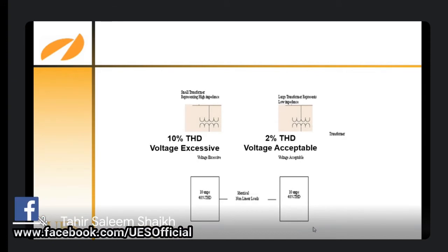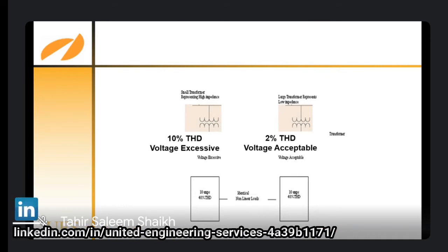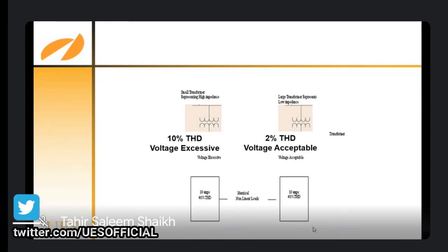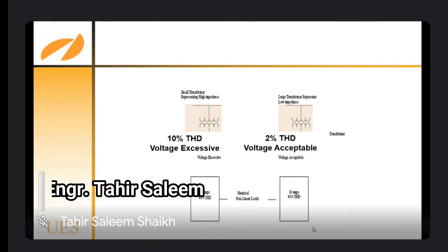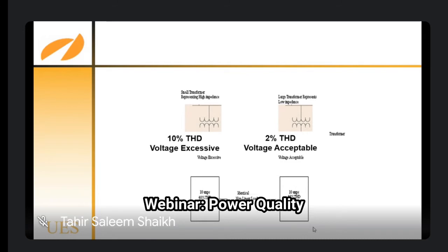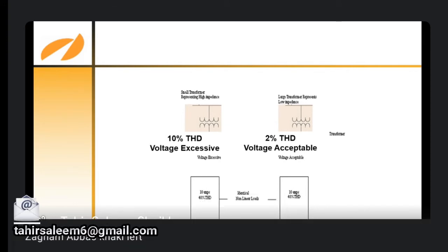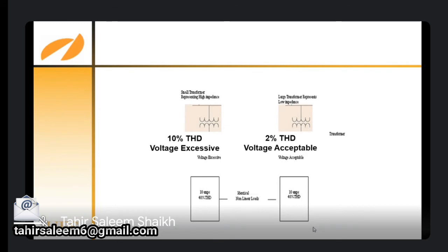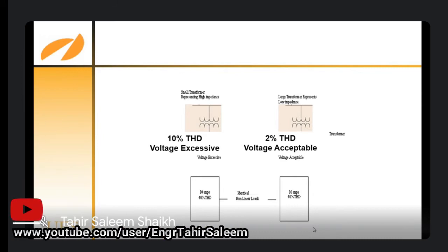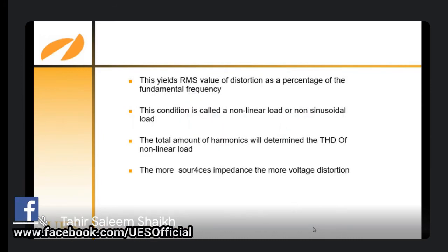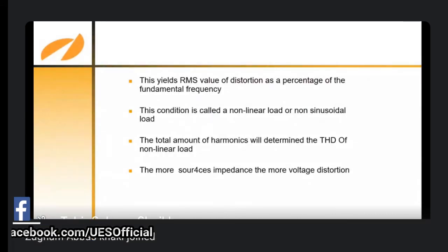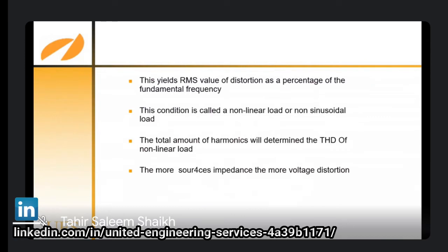If the voltage is 415 volts, go for a 500 volt capacitor selection. For transformer selection, if you don't know the K factor of the transformer, then instead of 100 kVA you can go for a 120 or 130 kVA transformer, for example. This will reduce the heating impact of the harmonic current and voltage. Dielectric strength will increase; you can select a higher dielectric strength for the insulation level. This is the easiest, but there is some cost impact. This yields the RMS value of the distortion as a percentage of the fundamental frequency. The condition is called a non-linear load or non-sinusoidal load. The total amount of harmonics will determine the THD of the non-linear load.